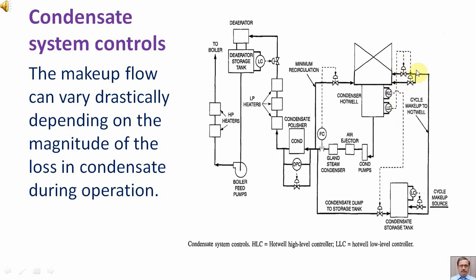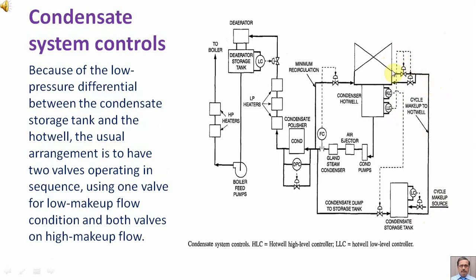The make-up flow can vary drastically depending on the magnitude of the loss in condensate during operation. Because of the low pressure differential between the condensate storage tank and the hot well, the usual arrangement is to have two valves operating in sequence — using one valve for low make-up flow conditions and both valves for high make-up flow.